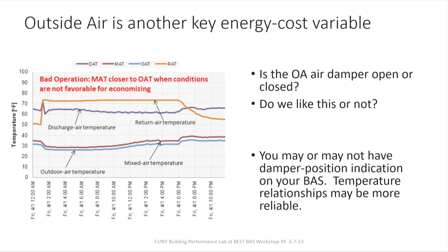Now, having heard that explanation, it probably becomes crystal clear to everyone in the room that with the mixed air temperature pinned up against the outdoor air temperature, it means we've got almost all outdoor air coming in. Very little mixing of the 70, 75 degree return air. So in a normal condition, we see the mixed air temperature somewhere up in the middle between outside air temperature and return air temperature. But in this case, when it pins close to the outside air, it means the outside air damper is stuck open. So if the mixed air temperature is pinned up against the return air temperature, what does that mean?